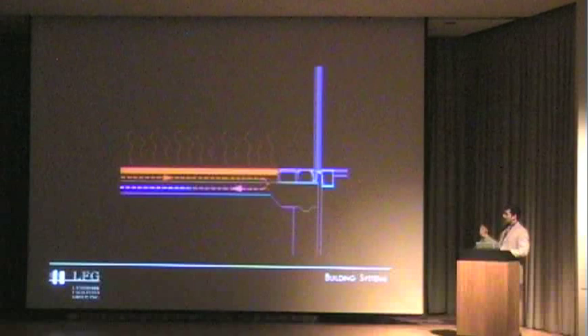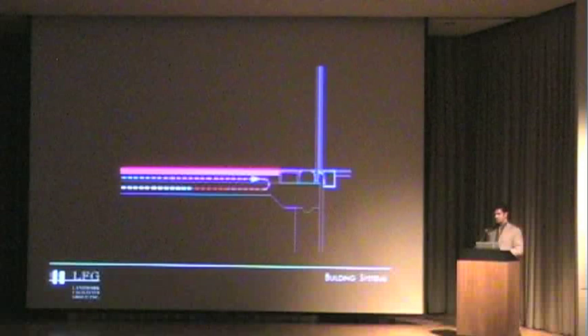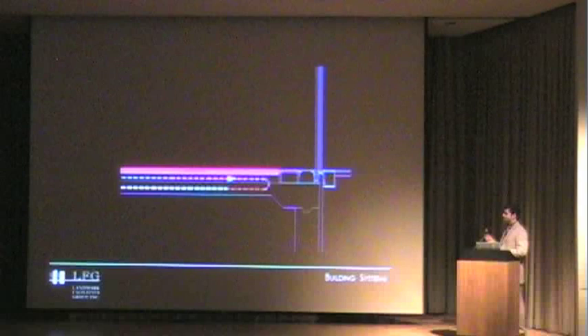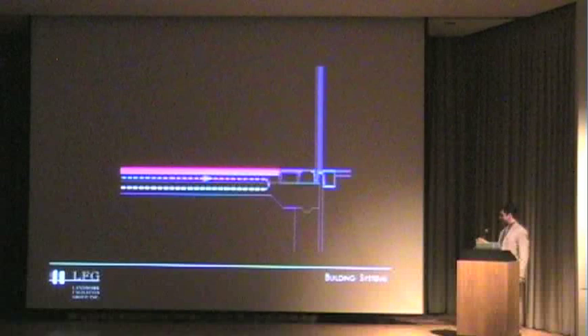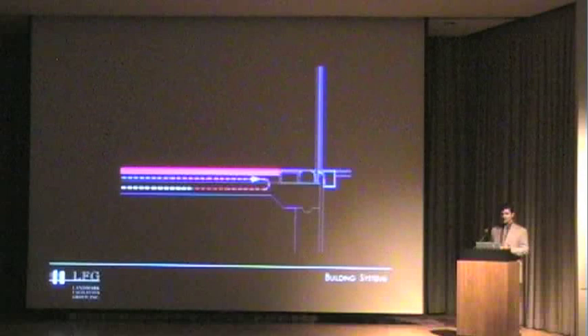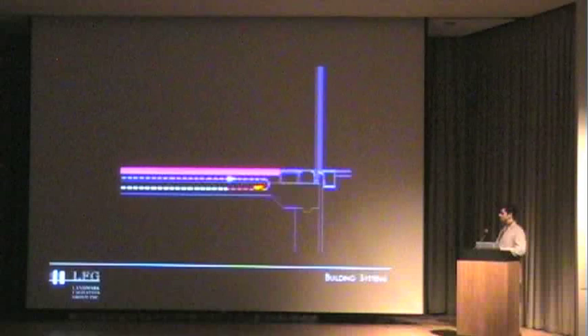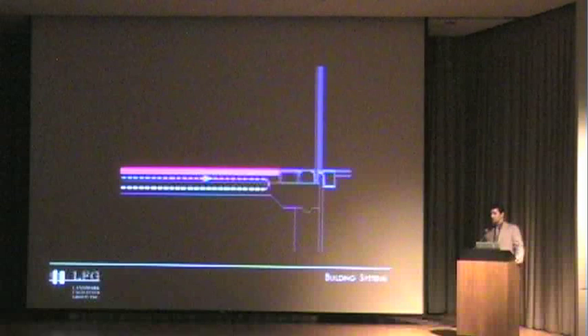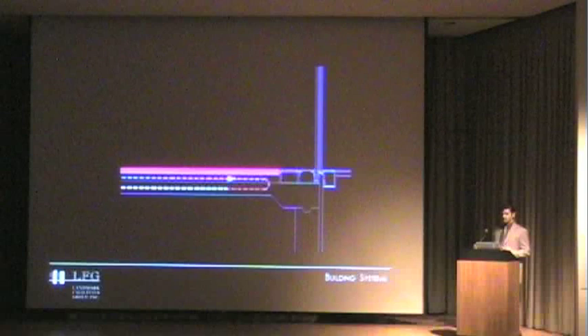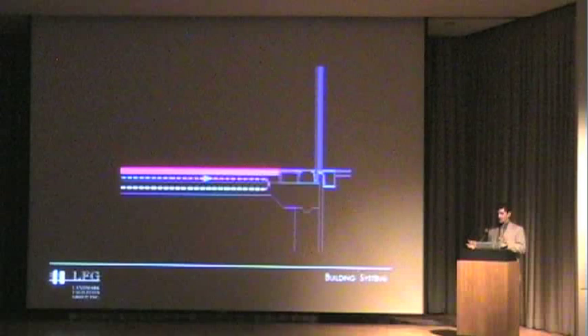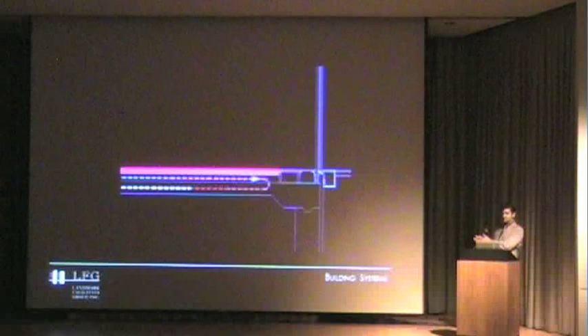By having this radiant system, we're also able to do what people are apt to call radiant cooling, but I prefer to call it radiant heat absorption. Essentially, as the exterior sun comes in and warms the floor, we don't want it to radiate into the space and add to our cooling loads. So we run tempered water through the radiant slab to draw away that solar heat and put it back into the system, taking that load out of the equation. Essentially, it takes our glass building and eliminates the solar portion, the glass load, which is huge when designing a system, because it allows us to reduce the size of the system and make everything much more energy efficient.